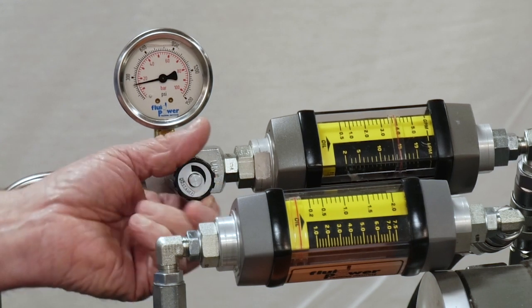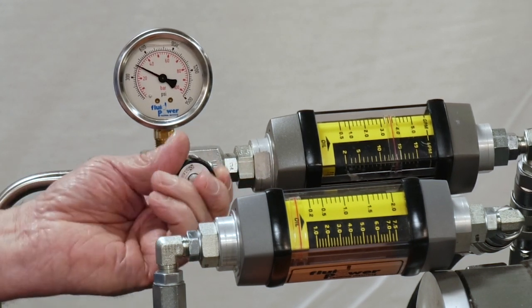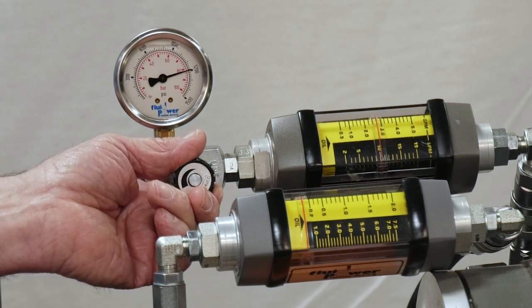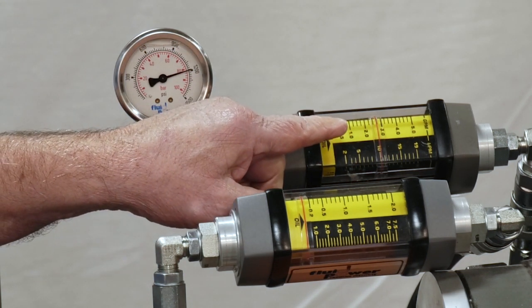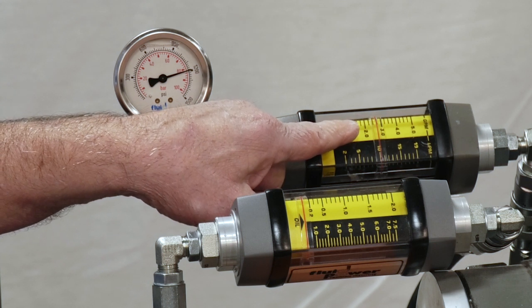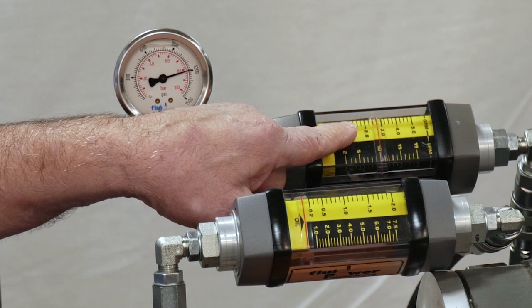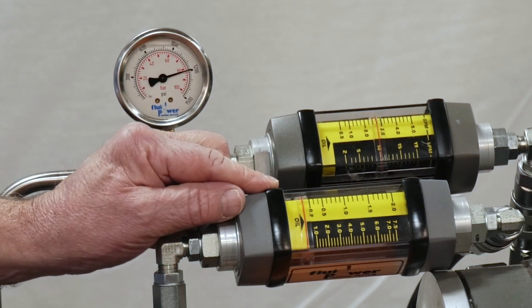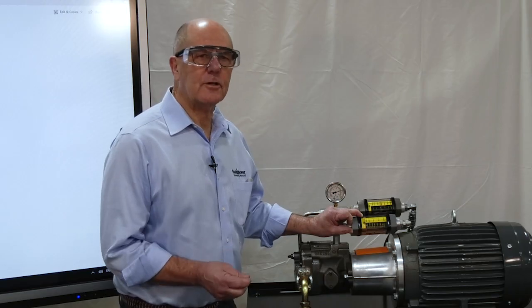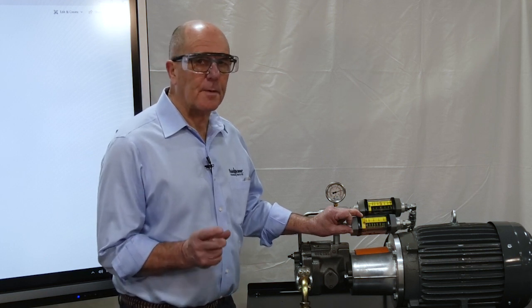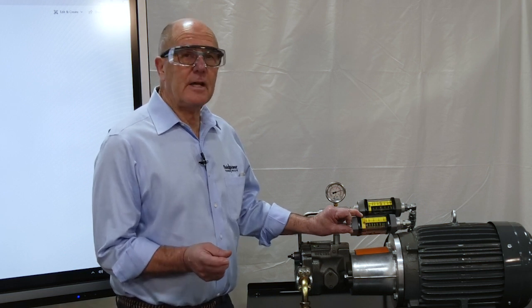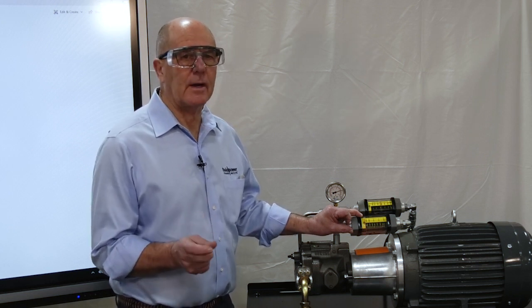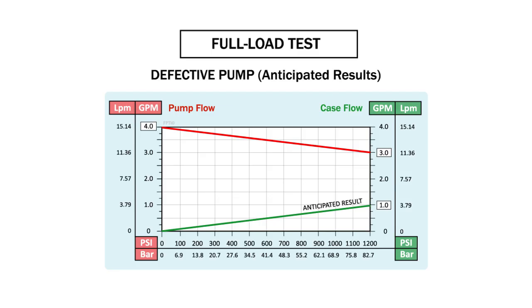Now I am going to load the pump back to 1200 PSI. I am starting to see a decrease in flow on the discharge side of the pump as I increase the pressure drop across the pump's clearances. At 1200 PSI, my flow has dropped to just below 3 gallons per minute on the pressure line, but I am not even showing 0.2 gallons per minute on the case drain line. According to the experts, pump flow and case flow are directly proportional — so if pump flow decreased by 1 gallon per minute, case flow should have increased by 1 gallon per minute. But that is not what happened.